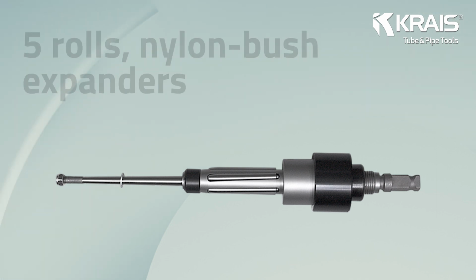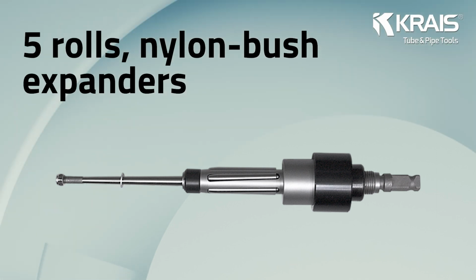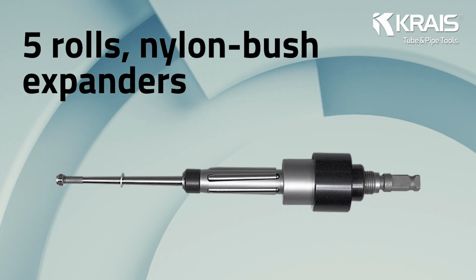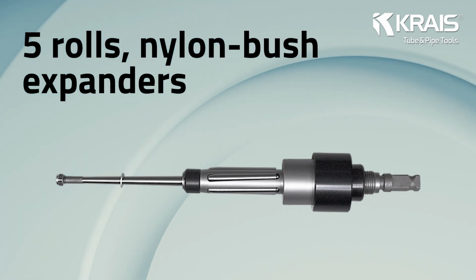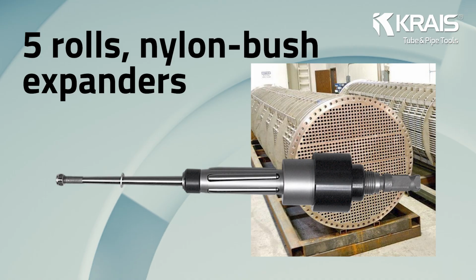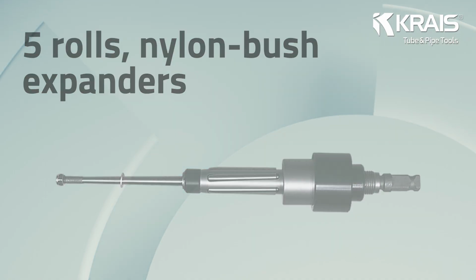KRAIS 5-roll expanders with a nylon bush reduce the risk of surface marking ahead of the working cage. They are used where the tube material is surface sensitive and quality requirements are high, commonly with titanium tubing.